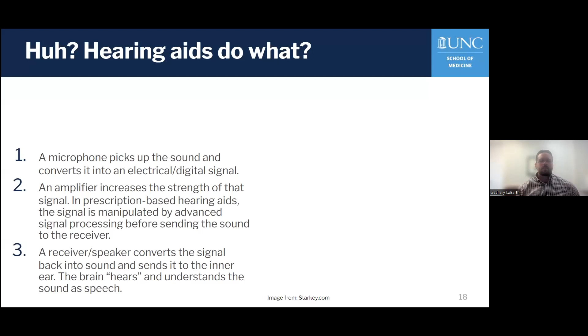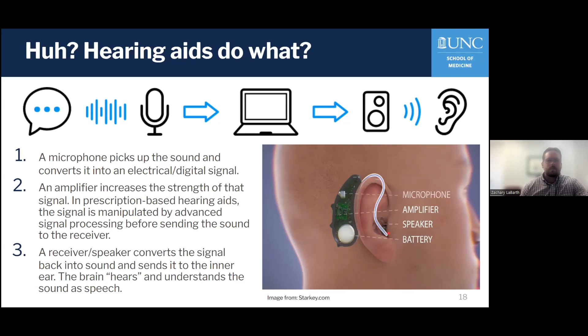Breaking it down, a microphone picks up the sound and converts the sound into an electrical or digital signal. An amplifier then increases the strength of that signal. In prescription-based hearing aids, the signal is manipulated by advanced signal processing before sending the sound to the receiver, which is the portion of the hearing aid that's located within the ear. If you follow along with the laser, you can see how it progresses from over the ear, and the receiver is encased inside the ear. The receiver or speaker then converts that signal back into sound and sends it into the inner ear. The brain hears and understands this signal or sound as speech.